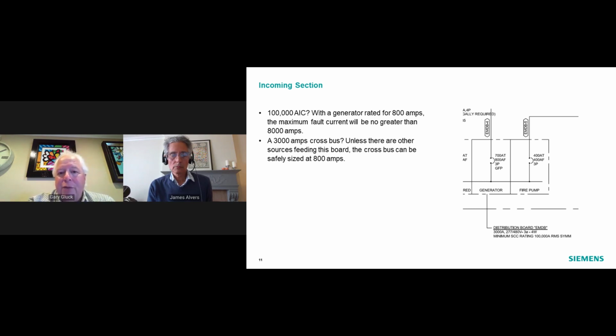That's going to be the maximum. So if we look at an 800 amp output from the generator, the maximum fault current for that switchboard is ever going to see is 8,000 amps. So going with 100,000 is a bit overkill. There is a substantial cost savings tailoring the distribution closer to 8,000.